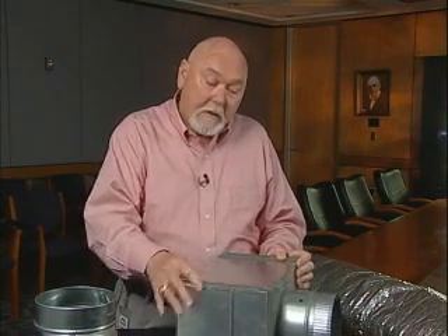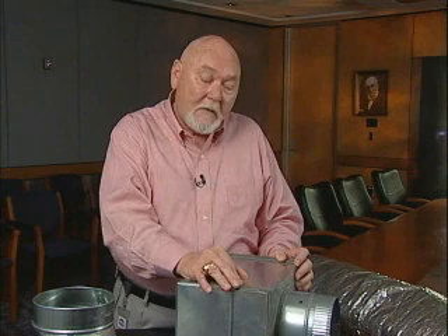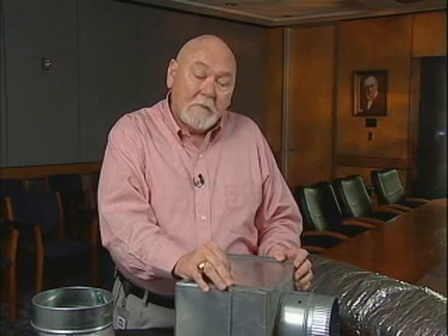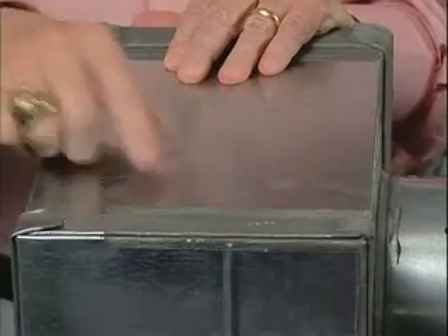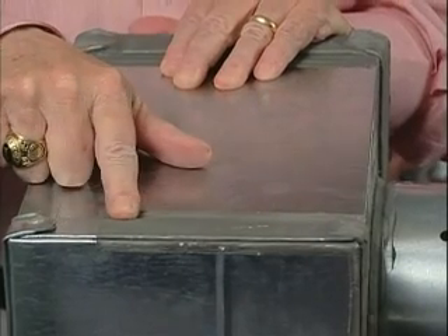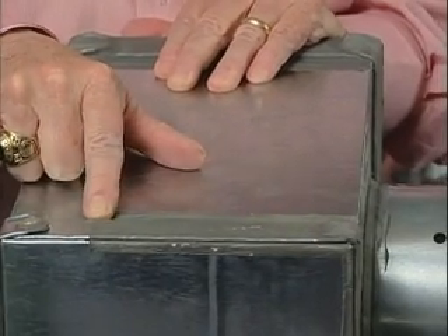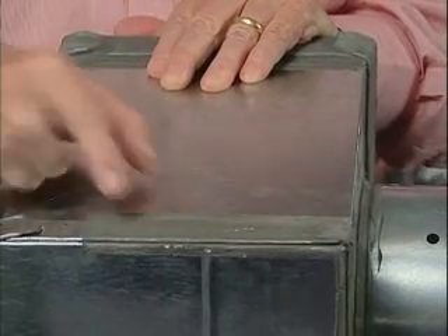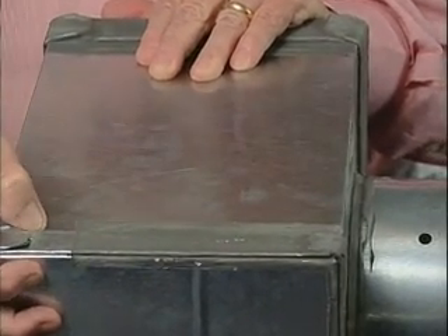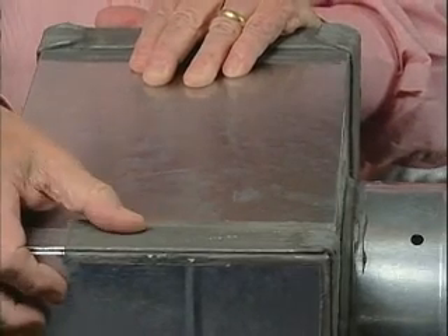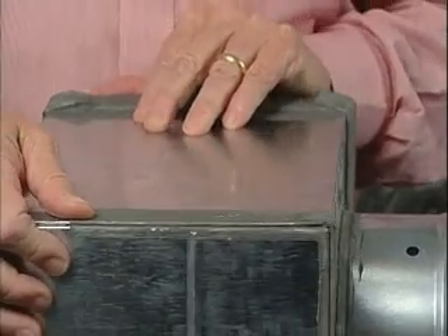What you want to do is ensure that each joint, every place that this metal is put together, has a product called mastic used on it. And mastic is a paint-on material that dries over a period of time like a cast. So it seals off the ductwork. This is what mastic looks like when it's cured. It seals off this joint, so you can't suck any air where the metal's put together. You want to ensure that all of your joints are sealed.